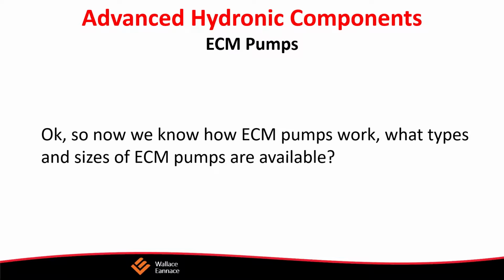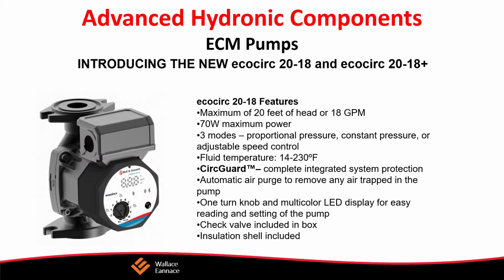These are all standard wet rotor pumps that have maybe 85 watts of power. See, these circulators actually consume this heating system. It's a 10,000 square foot house, and they had 40 circulators consuming 90 watts each. So the design heating load was 400,000 BTUs per hour. So the distribution efficiency was 400,000 BTUs an hour divided by 40 times 90 watts, which is 111 BTUs per hour per watt.